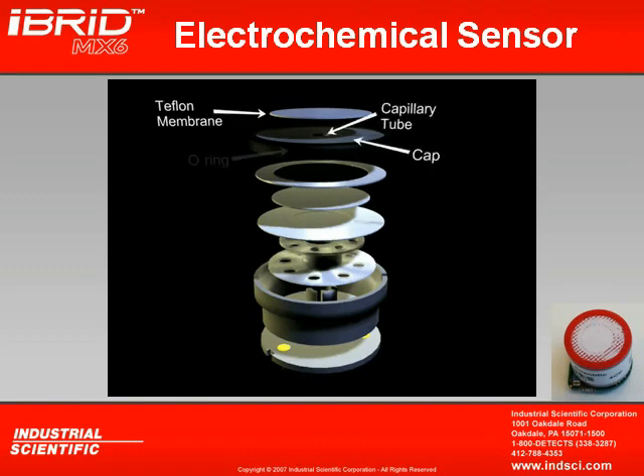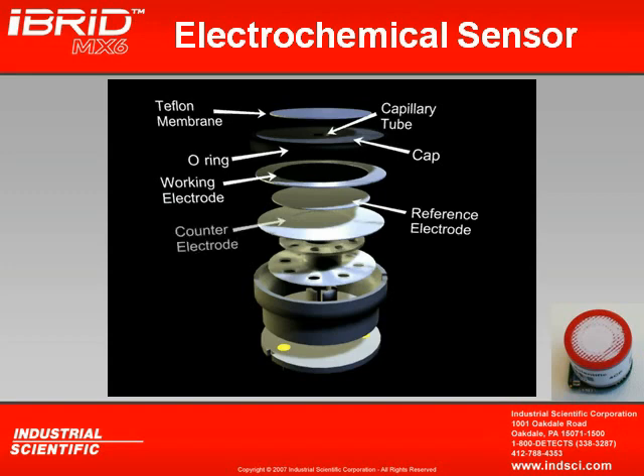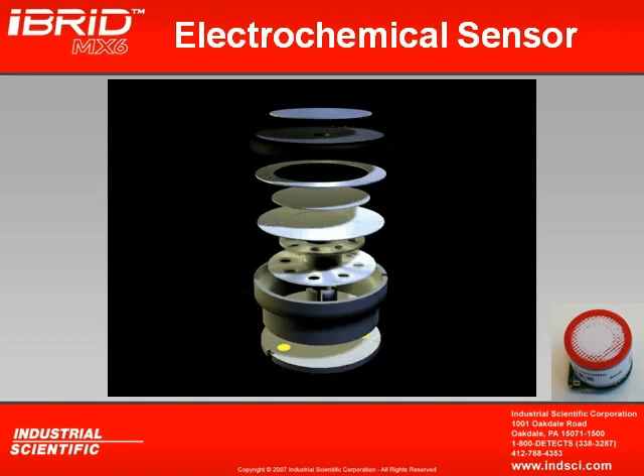The gas will then come in contact with 3 different electrodes: a working electrode, a reference electrode, and a counter electrode. And at the very bottom of your electrochemical sensor is the electrolyte reservoir. Now your electrolyte reservoir holds about 1 cc of 40% pure sulfuric acid. The last thing we want to do is go opening up these sensors to see if there are little monkeys running around inside. It's really not all that interesting inside of an electrochemical sensor, because where my gas is being detected is on those 3 electrodes.